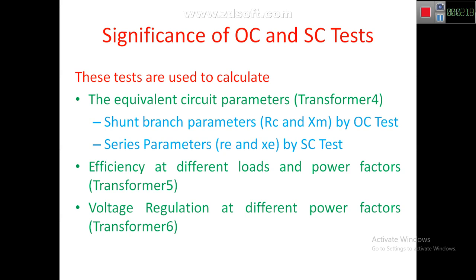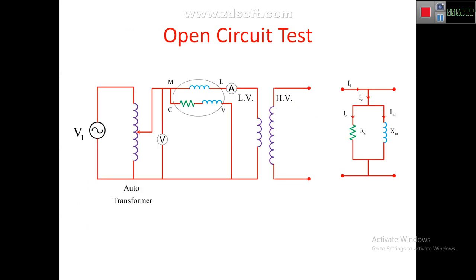We conduct the open circuit test on the LV side, meaning the HV side is open circuited and all instruments are connected to the LV side. In the circuit diagram, there is an AC voltage source, followed by an auto transformer to provide the necessary voltage, a voltmeter to measure the applied voltage, a wattmeter to measure power, and an ammeter.